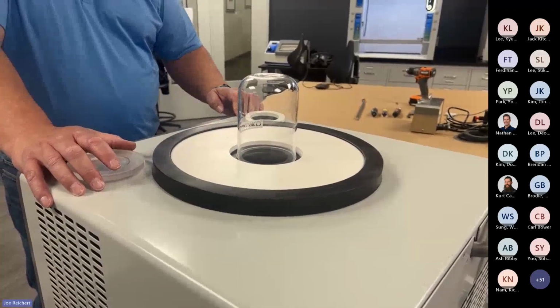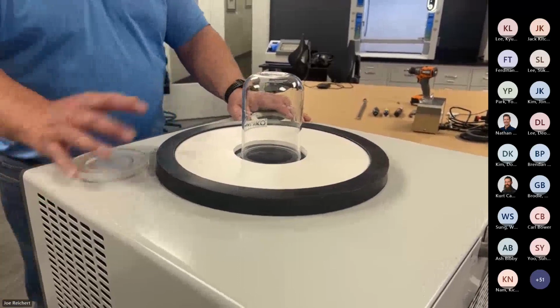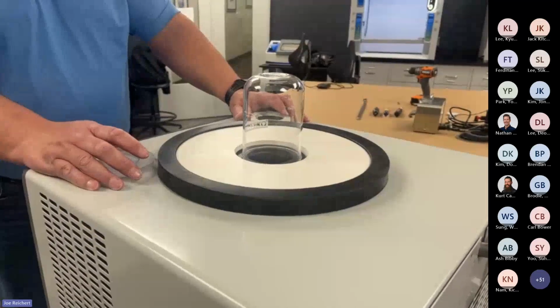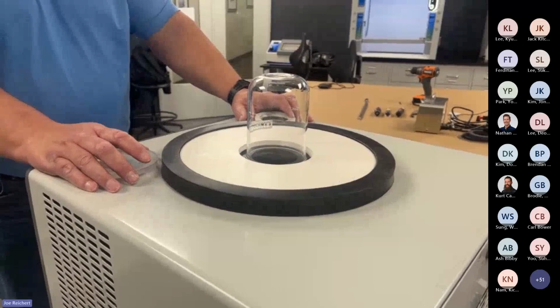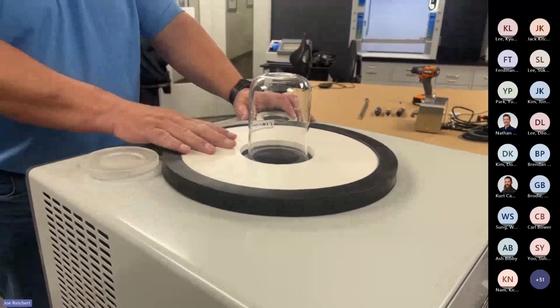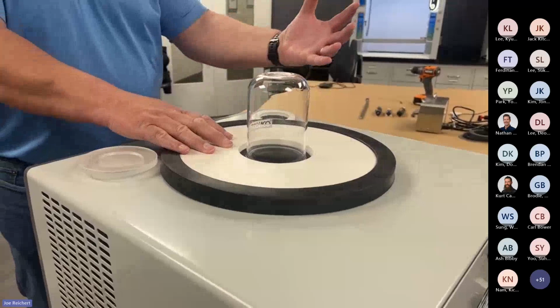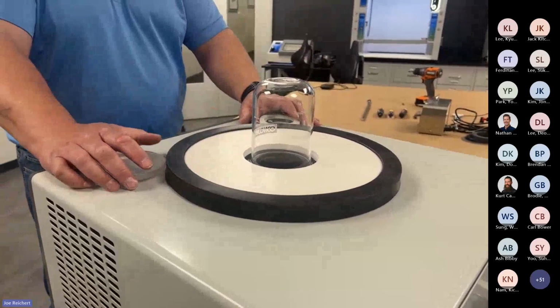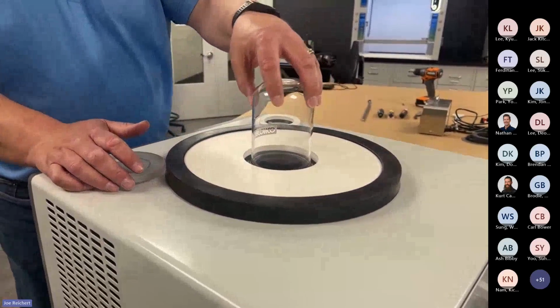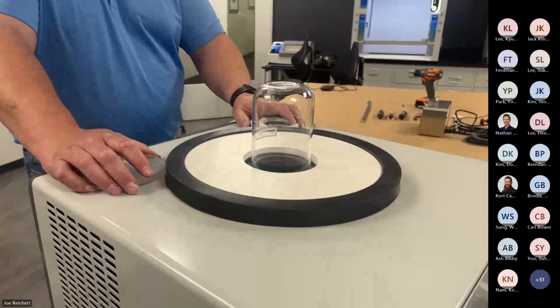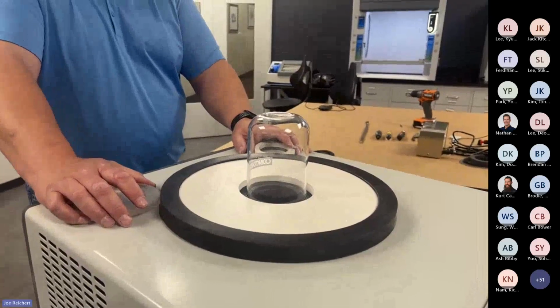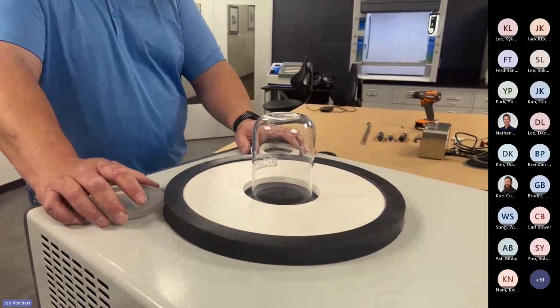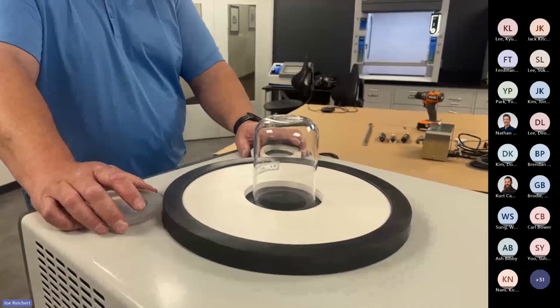Then you just turn on the vacuum. The flask will take all the pressure that you can handle from the pump. There's no difference in having the flask here or on your 12-quart chamber. It's all the same pressure. You see, immediately it's held down. And here you should get a pressure on your display in just a few seconds to maybe a minute or two.